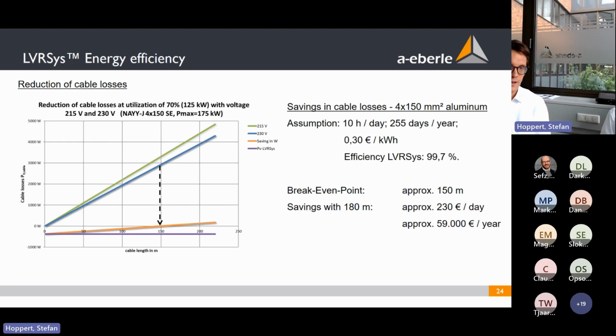In this case, we installed our system, and the orange line below shows the difference from the beginning over the length of the cable. At 150 meters, you see the break-even point, because the purple line below shows the losses we have through our LVRSys, which are quite low because the efficiency is 99.7%. But if you consider how many meters you have in your factory from the station where you connect till the end, from this point on you can even save money if you have longer lines and you boost your voltage up to 230.